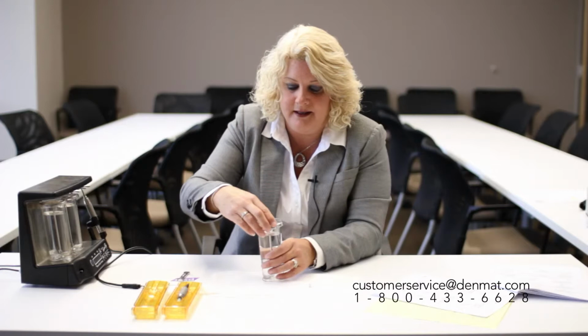So we would take that piece off and we would put this back in to the bottle, and to determine if that's what the issue is, turn the unit back on, make sure that you are on this bottle, and does the water flow freely through. If it does, we need to make sure that we clean this piece out that we spoke of with the screen, using a toothbrush or a small brush to clean the area out, and use the air water syringe to blow any debris out that may be stuck or lodged here.